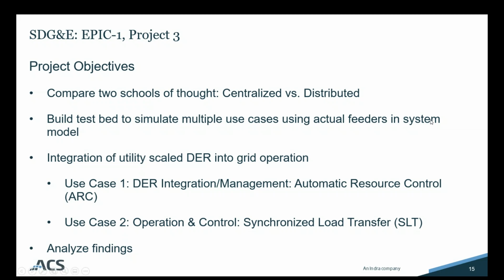So, some of the project objectives. First, they wanted to compare two traditional schools of thought, centralized versus distributed control. They hypothesized that as a higher penetration of smart field devices comes onto our systems, it's logical to have control closer to those intelligent devices, thus leading to a more distributed control architecture. Also, the distributed control architecture should reduce latency, to be able to react to events much quicker than a centralized system. Also, by nature, a distributed control approach should be more reliable compared to a centralized one.